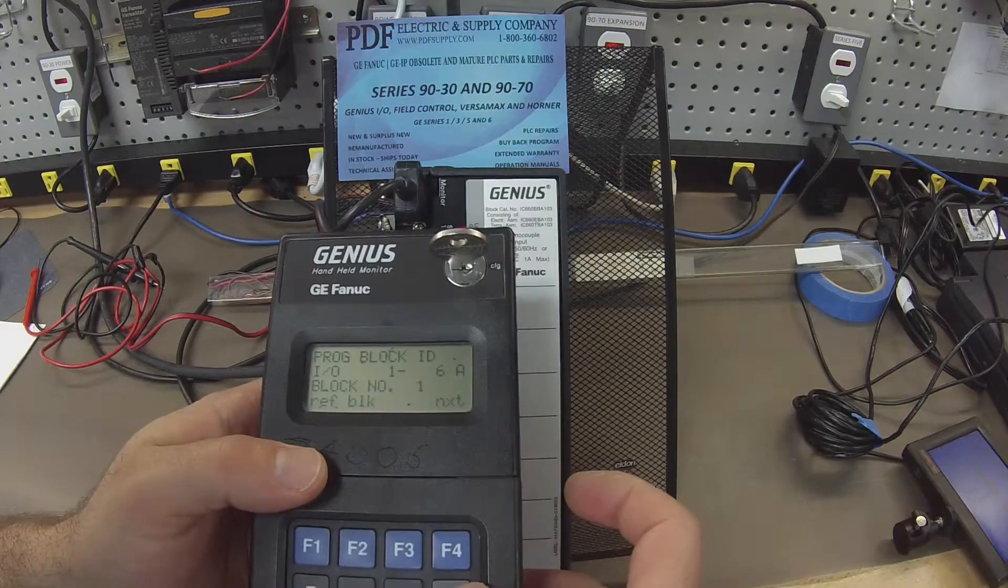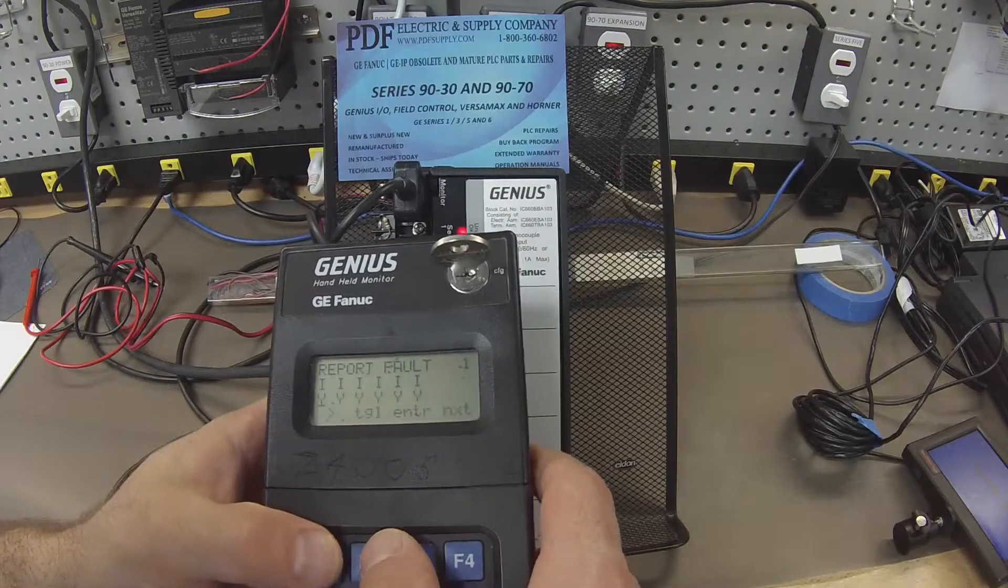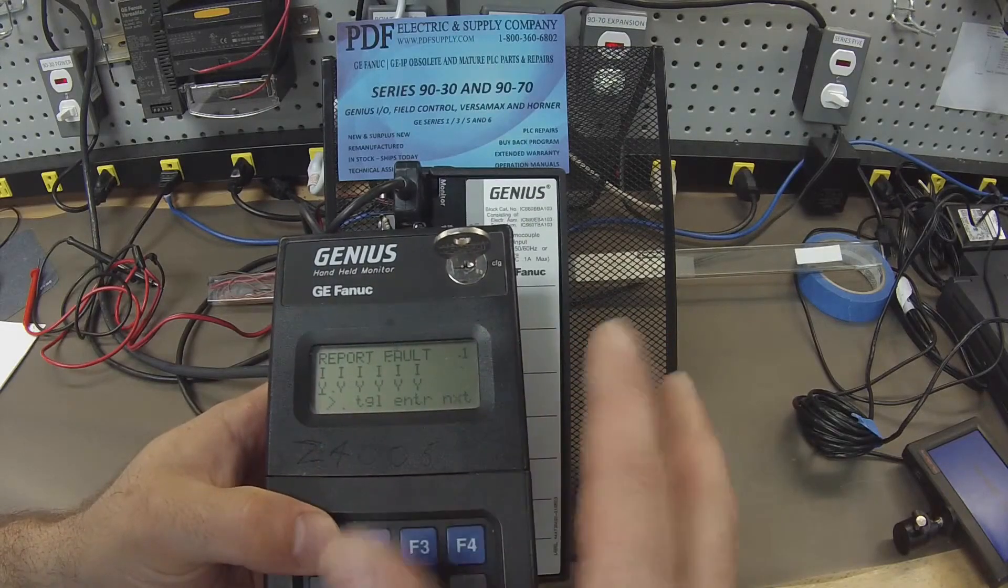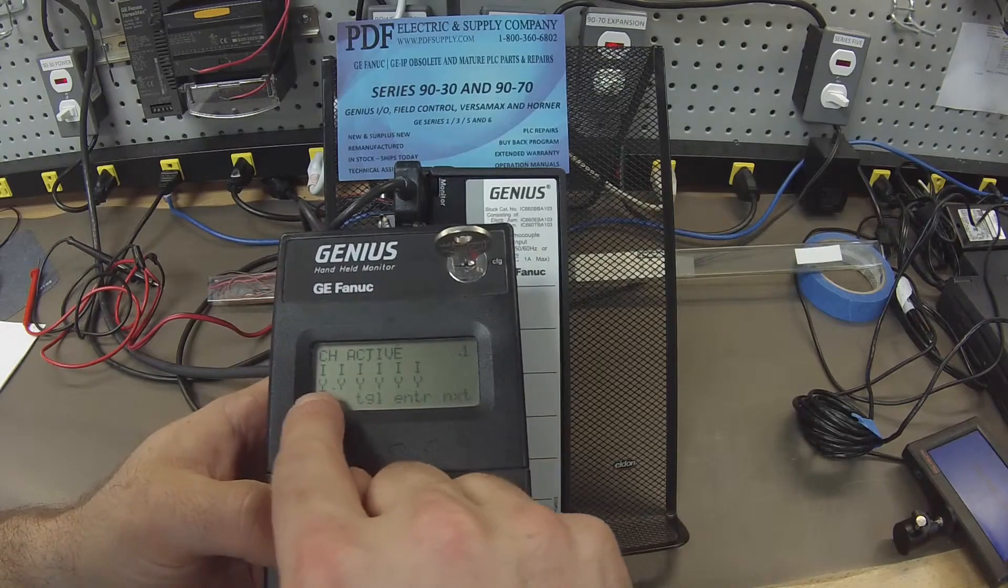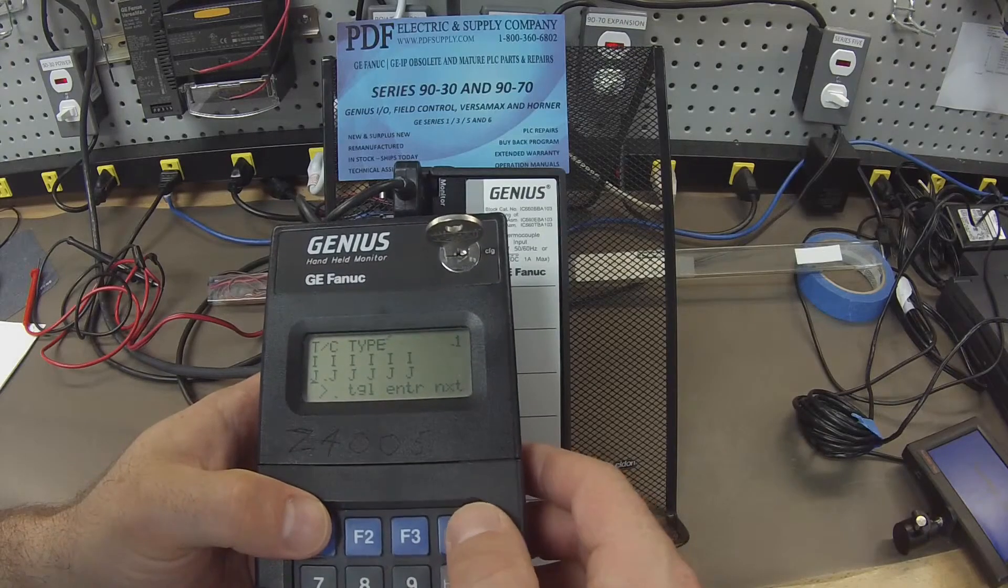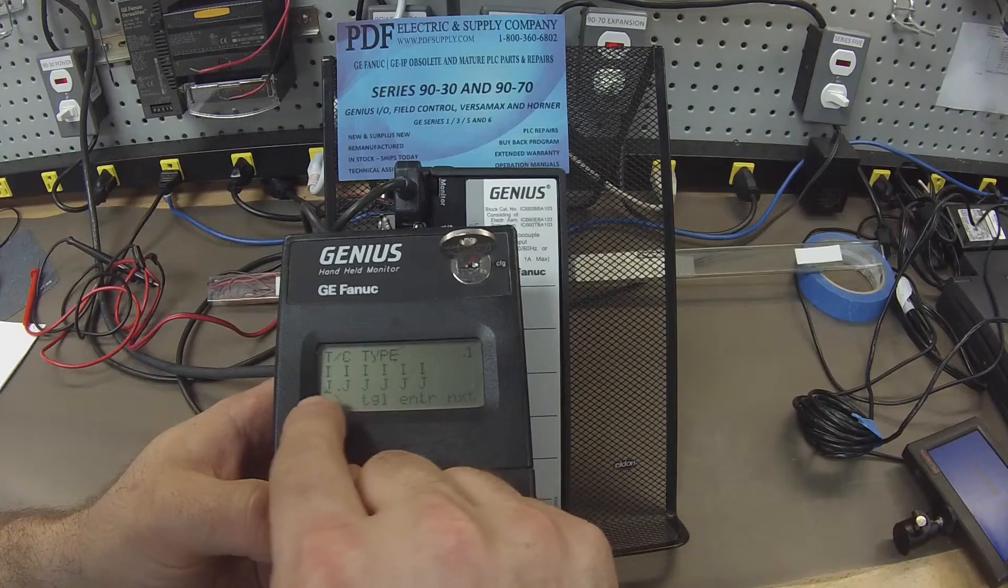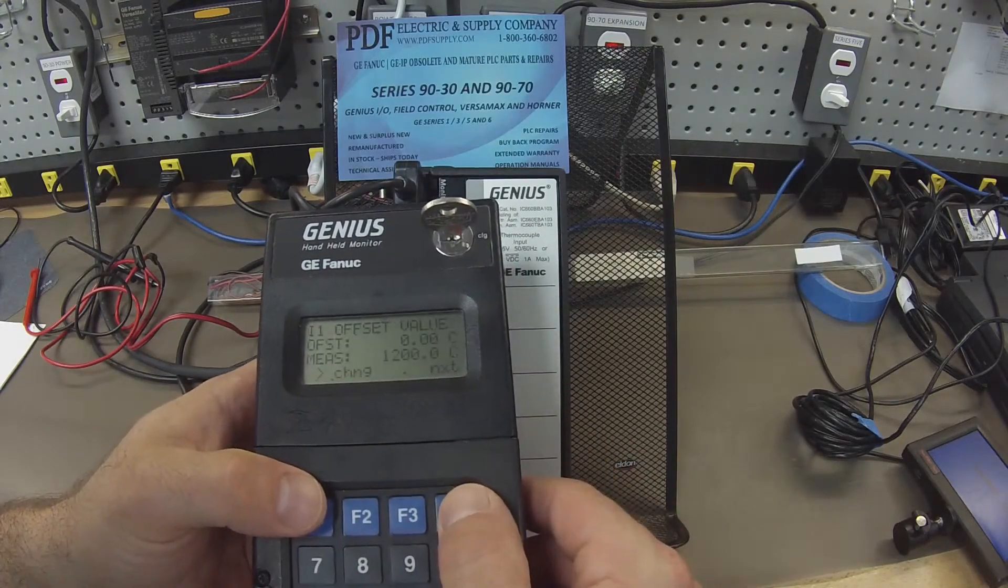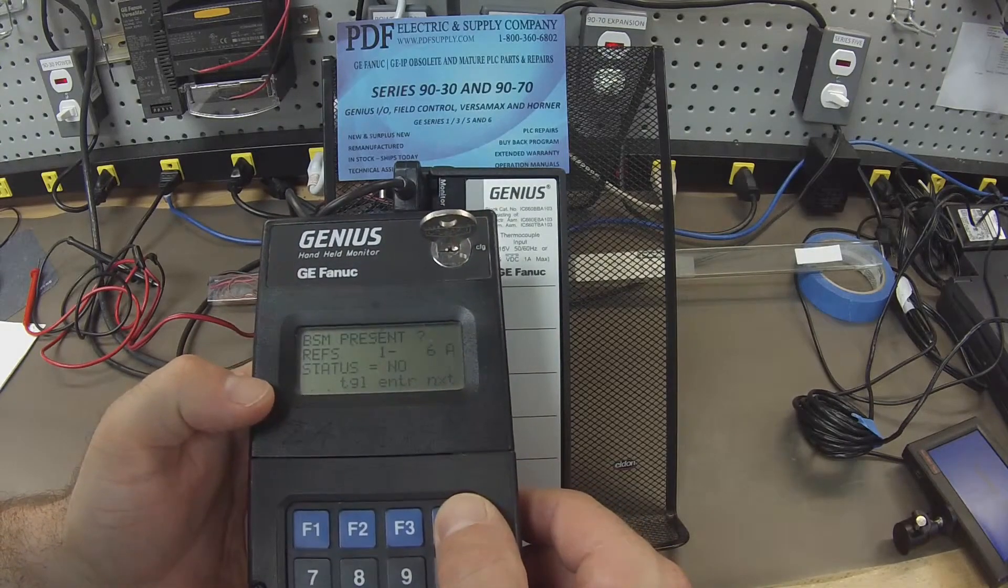Alright, and then I go back to home, F3 configuration, F2 configure block, and I have everything set to factory settings on the Genius block. You may have different settings, which is fine, but I do want to test every channel, so I have all these toggled for yes. The thermocouple I'm using, as I mentioned before, is type J, TC type J thermocouple, and those are all selected properly.